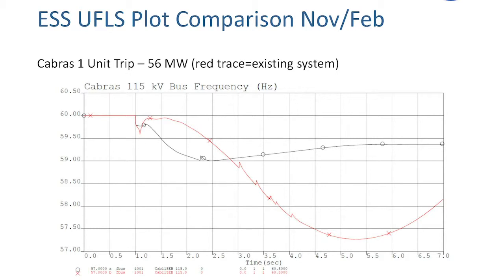You can see you trip a generator, you go down. In this particular system, in this particular simulation, you would trip 3 stages of under-frequency load shedding, and then you would come back and recover to 60 hertz. So this is one of the benefits of energy storage in an islanded power system. And hopefully you can see how critical energy storage is in a power system, especially as they move towards renewables. I think that's my last slide.